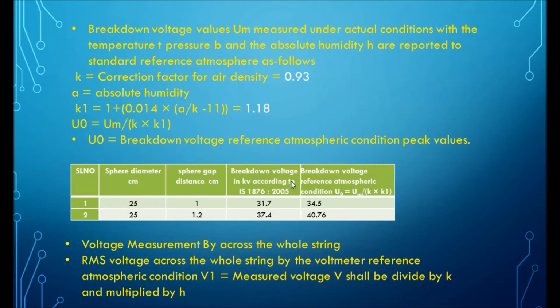But today the temperature and pressure are different. Then the flashover voltage changes to 34.5. If you set the distance to 1 cm, the flashover voltage is 34.5 kV in peak value. And if you set the distance to 1.2 cm, then the flashover voltage according to the atmosphere is 40.76 kV. This is the peak value.